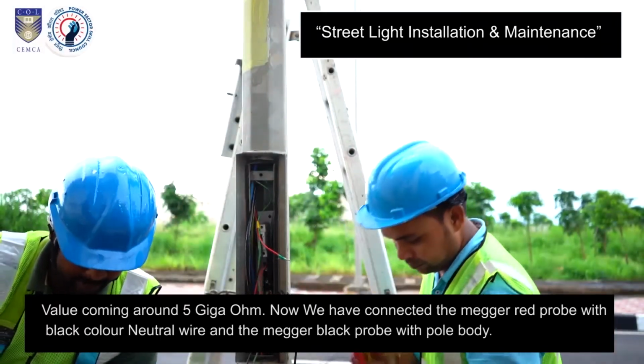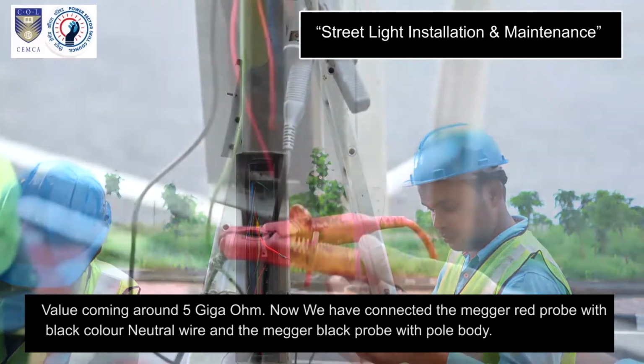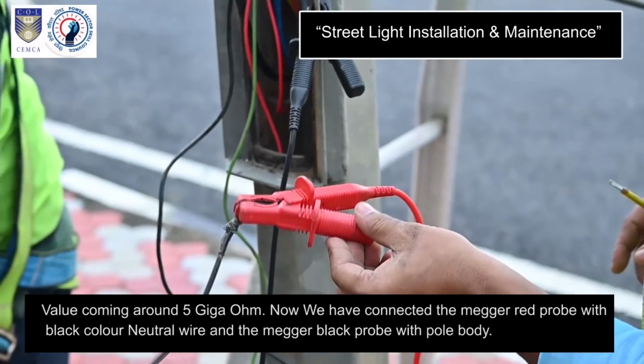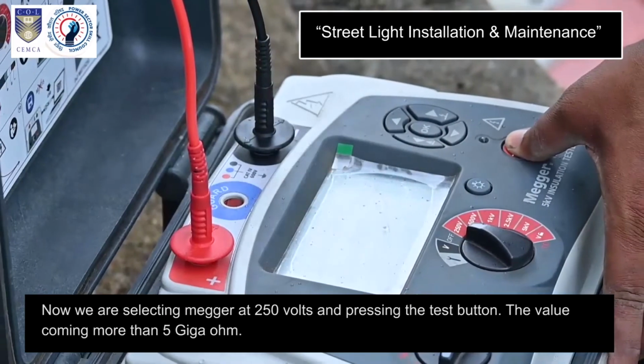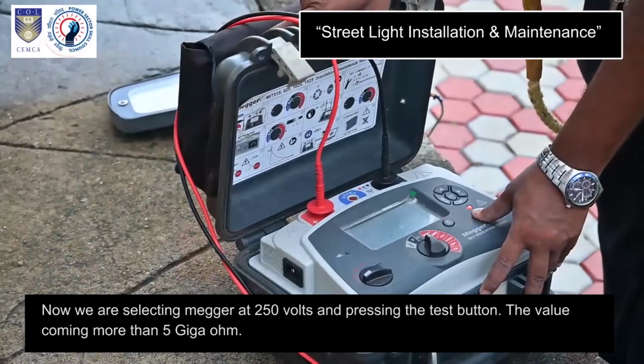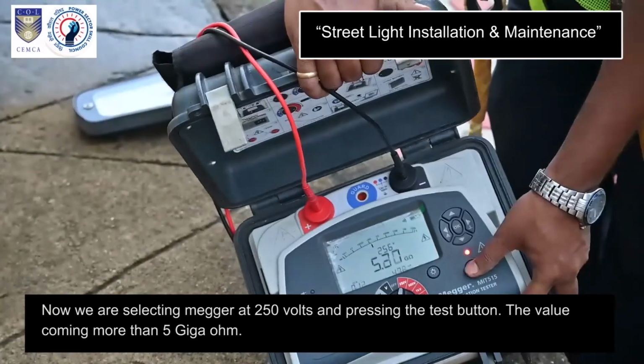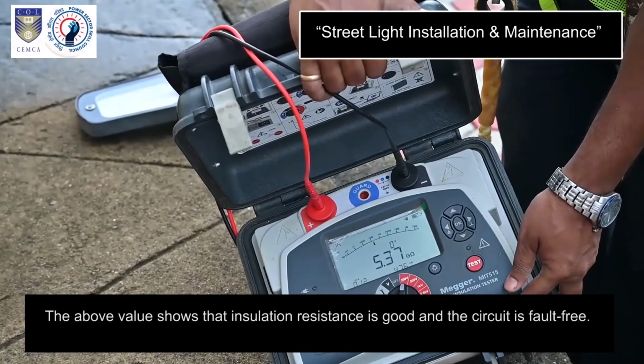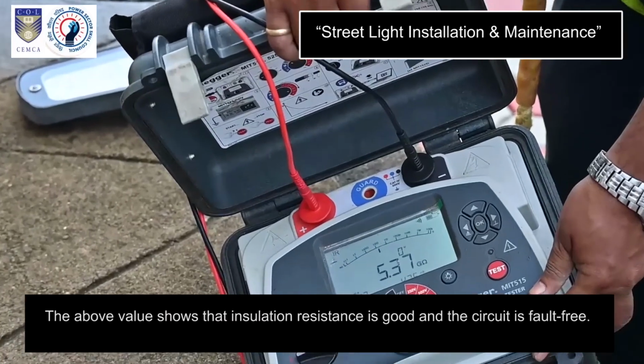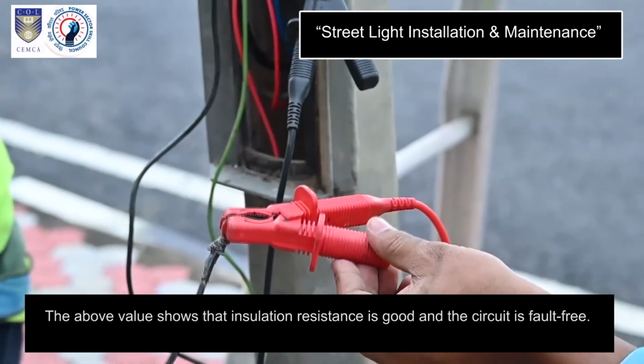Now we have connected the Megger red probe with the black color neutral wire and the Megger black probe with the pole body. Now we are selecting Megger at 250 volts and pressing the test button. The value coming more than 5 gigaohm. The above value shows that insulation resistance is good and the circuit is fault free.